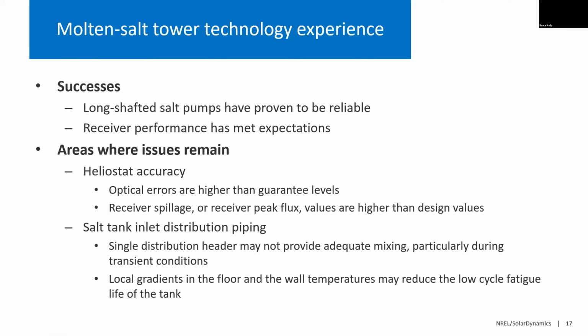So some things have worked really well in these plants. And interestingly, these are the ones that might be considered the high risk items. One is the salt pumps, and the second one is the receiver. Salt pumps are typically supported above the tanks and draw suction from near the bottom. And the pump shafts here are really long, 12 to 15 meters, with power ratings, in some cases, above 1 megawatt. And so this seems like an odd design, but they've worked really well. And at Crescent Dunes, they have 9 pumps with no problems in the several years that the plant ran. Interesting performance on the pumps, not really expected.